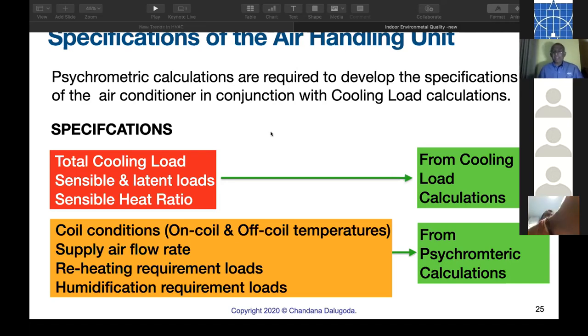Then reheating capacity. Nowadays people sarcastically say, oh, why reheating? Waste of energy. Of course, ASHRAE 90.1 suggests reheating not be used. But reheating is required in some instances to reduce relative humidity, not the moisture content, relative humidity. ASHRAE says don't use electric heating, but other methods. We have so many other methods, but we have to calculate the reheating component to maintain RH. Then humidification requirements, all that will need psychrometric analysis. So this is how we find the specifications. So you have some notes, a few things for us to go through before our main lesson.